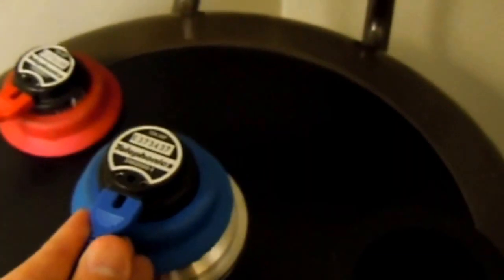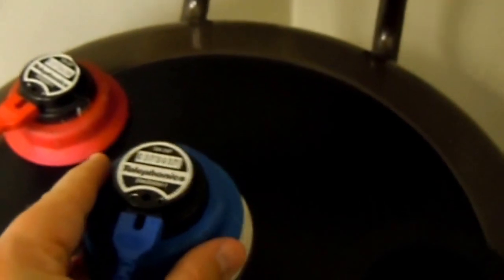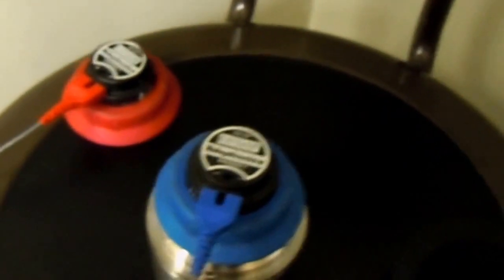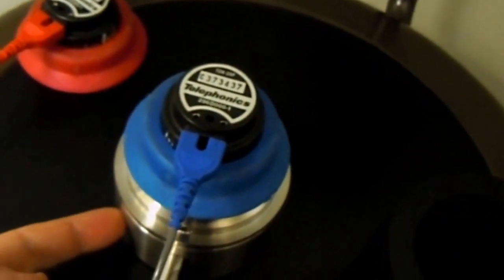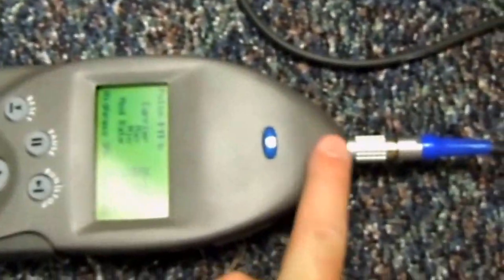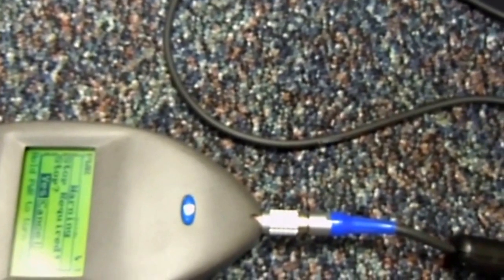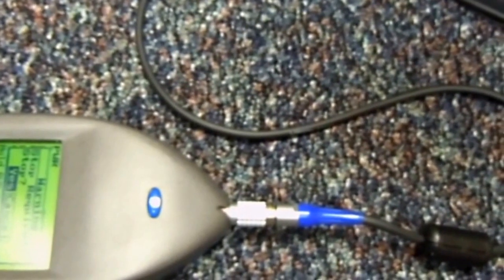Come back here to our calibration booth. We're going to start with the left ear. We're going to put the left ear on the coupler, which is attached to the artificial ear, which is connected to the preamplifier here. The preamplifier is connected to our sound level meter. So we're going to turn that on.